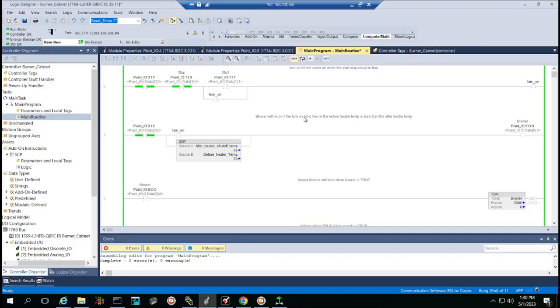All right, so now we're going to get into the programming of this thing. So this first rung here is just a simple start-stop circuit, and I'll turn on this turn-on bit. And this turn-on bit will turn on the blower as long as the e-stop isn't pressed. And then we have this greater than. So I have a temp probe after the heater and before the heater. So when we want to stop this thing, we don't want all that heat in the heater coils to stay there, maybe melt something or start a fire if there's no air blowing through it. So the blower will keep blowing if the after heater temp is greater than the before heater temp.